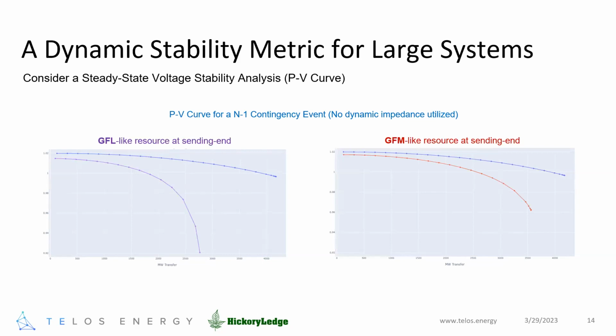What we can see is if we now introduce a dynamic impedance to the resources, tuned and associated with a particular resource or category of resources, it changes the PV curve substantially. For grid following resources, on the left, where you're not controlling the terminal voltage as well, you have that larger impedance, and the PV curve falls off a lot sooner. Whereas for a good voltage regulating resource like a grid forming inverter, that impedance is smaller, and the PV curve remains closer to the idealized curve for longer.